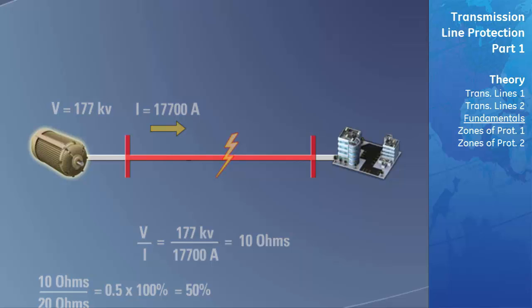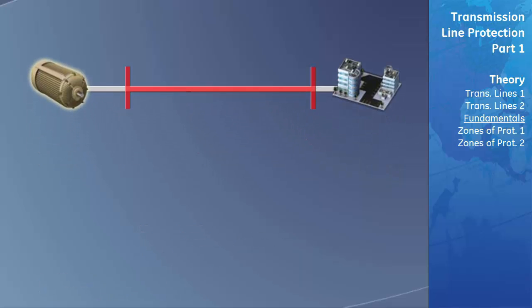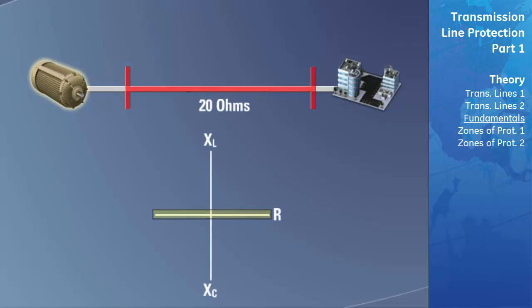The impedance of the line is often drawn on an RX diagram. The x-axis represents the resistive component of the impedance of the line. The y-axis represents the inductive component of the impedance of the line in the positive direction and the capacitive component of the impedance of the line in the negative direction. The impedance of a transmission line is inherently mostly inductive; therefore, if you were to plot the impedance of the line on this graph, it would be very close to the y-axis.